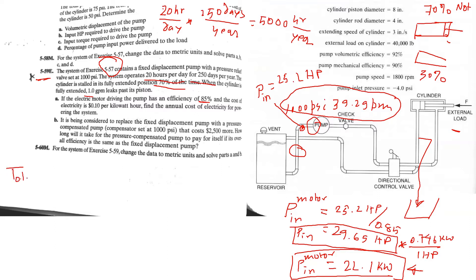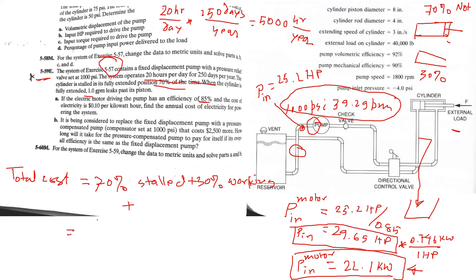To calculate the total yearly cost, we consider two periods: 70% of the time the cylinder is stalled and does no useful work, and 30% of the time it is working. When the cylinder is stalled, it actually develops higher pressure — up to the pressure relief valve setting. When running, the system operated at about 908 psi. But when stalled, the system develops up to 1,000 psi, so it actually takes more power when it is not working.